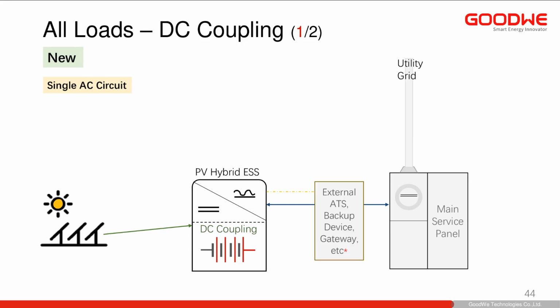And finally, for our views today, although there are more possibilities here, I've drawn something that absolutely cannot happen. If you had this set up, your customer is not getting any backup power. If the ATS is put in this location, when the grid goes down, no power is going to make it to the main service panel. So if you don't have an essential loads panel and you're just doing this, your customer gets no backup power.